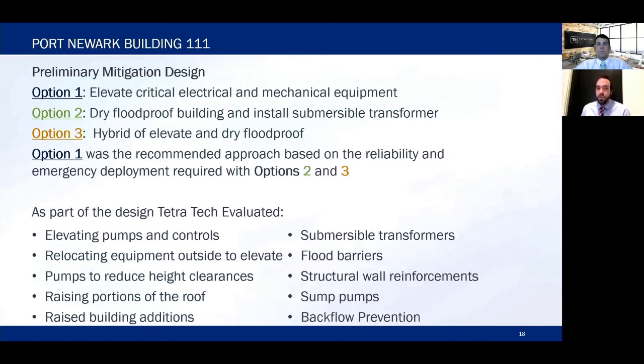We ended up going with the elevate option because the client really did not want to implement dry floodproofing measures, which require human intervention and have higher susceptibility to failure as opposed to simply elevating a product. That includes elevating pumps and controls, relocating equipment outside due to limited ceiling heights, and switching pumps from a vertical orientation to a horizontal one.